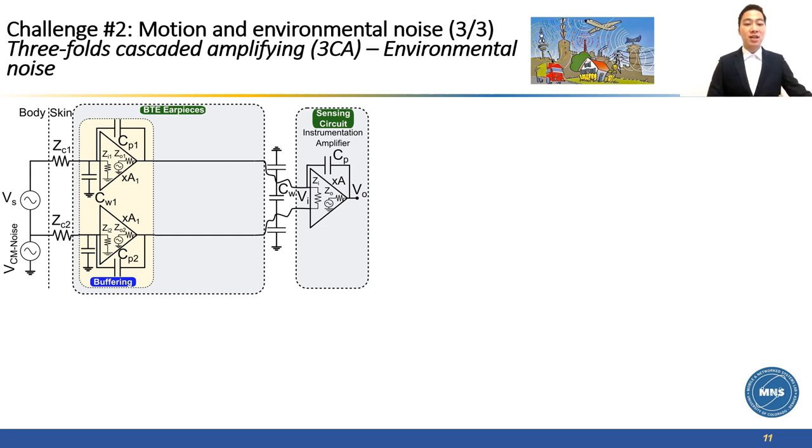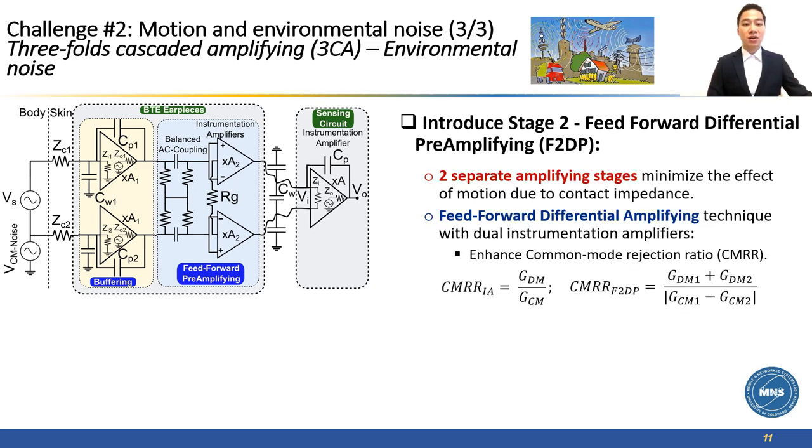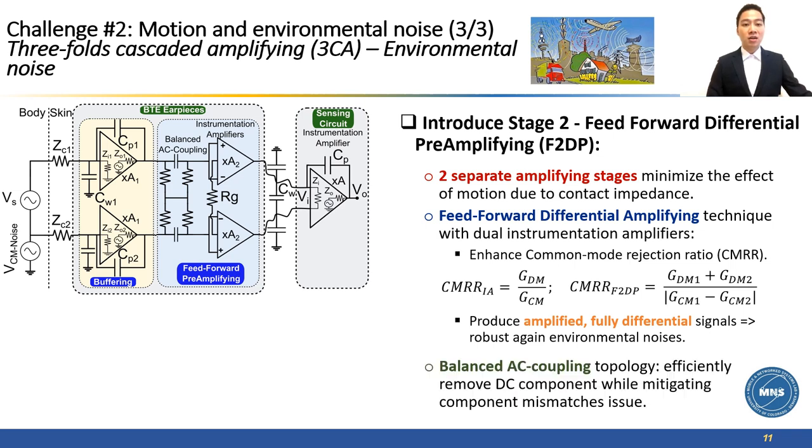To address the noise coupling from the environment, we will need to add another stage called feed-forward differential preamplifying, or F2DP, to amplify our behind-the-ear signal before driving the signal wire. F2DP technique is employed in our design, so we can enhance the common mode rejection ratio, which is the ability to reject noise coupled into the human body. Furthermore, it also produces amplified and fully differential output signal with robustness against environmental noise coupled into the signal wire. For F2DP to work, we need to remove the DC component inside the input signal. The conventional high-pass filter suffers from component mismatch, which compromises the common mode rejection ratio, so we use a balanced AC coupling topology to effectively remove DC component without suffering from component mismatch.